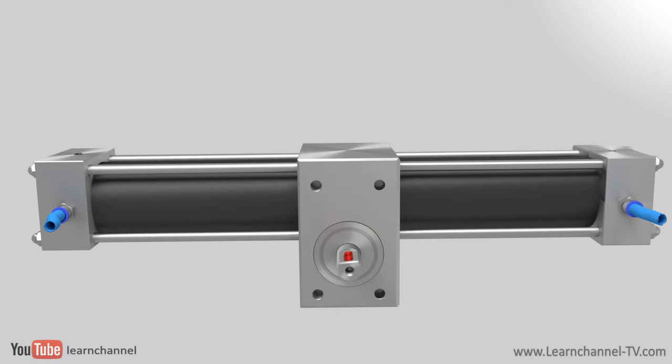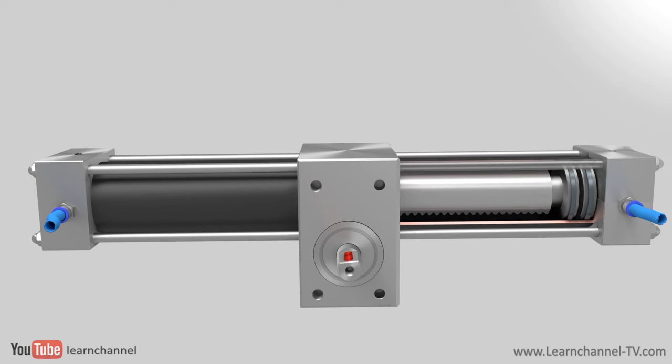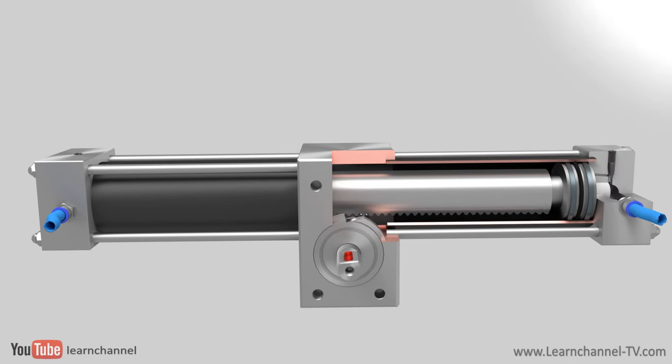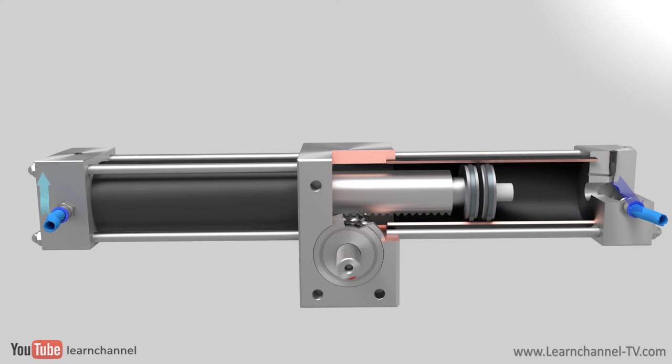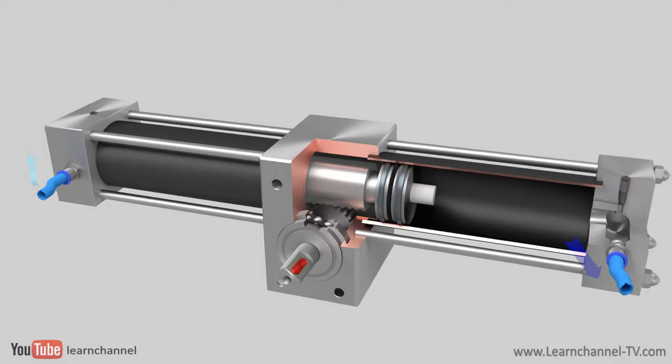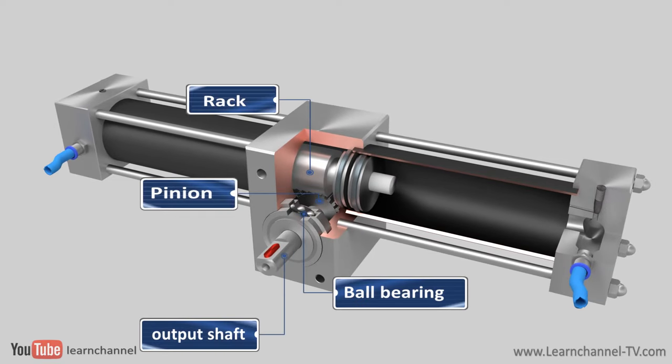Pneumatic rotary cylinder converts compressed air pressure into a rotary motion. One of the most widely used designs is the rack and pinion rotary actuator. A long piston with gear rack teeth meshes with a pinion mounted to an output shaft. The output shaft of this double-acting cylinder rotates counter-clockwise by pressurizing the right-hand chamber.